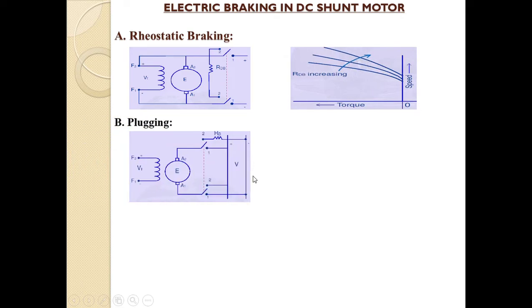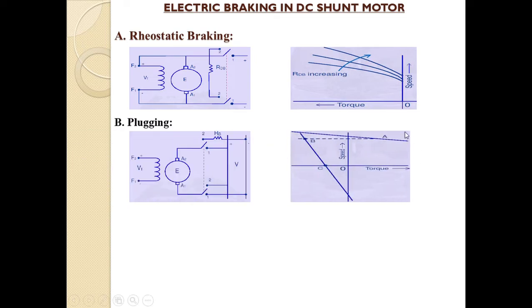Next is plugging in the DC shunt motor. In plugging, we interchange the polarities of the supply — the armature terminals change from plus/minus to minus/plus. This is shown in the corresponding circuit diagram. At the time of plugging, the torque travels from positive polarity to negative polarity and the speed is gradually reduced. After point C, the motor rotates in the opposite direction of rotation.